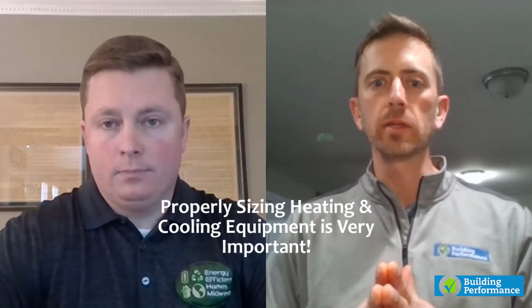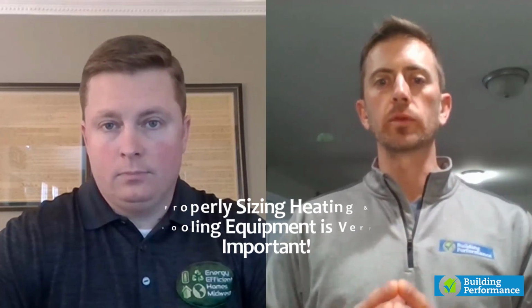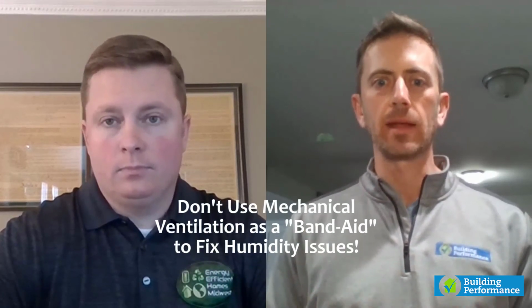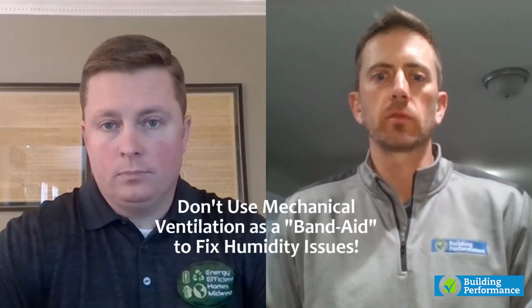One last thing I'll leave people with: mechanical ventilation was added as a requirement because there's a preconceived notion that as houses get tighter, you'll need mechanical ventilation at some point, and that's true as a blanket statement. However, I personally believe that if the HVAC contractor sizes their equipment properly, particularly the cooling side, that equipment will dehumidify the air inside the house better than using mechanical ventilation as a band-aid, which isn't really the purpose of removing moisture necessarily. An exhaust fan removes moisture from a bathroom, but it's not the best way to comply with that requirement.